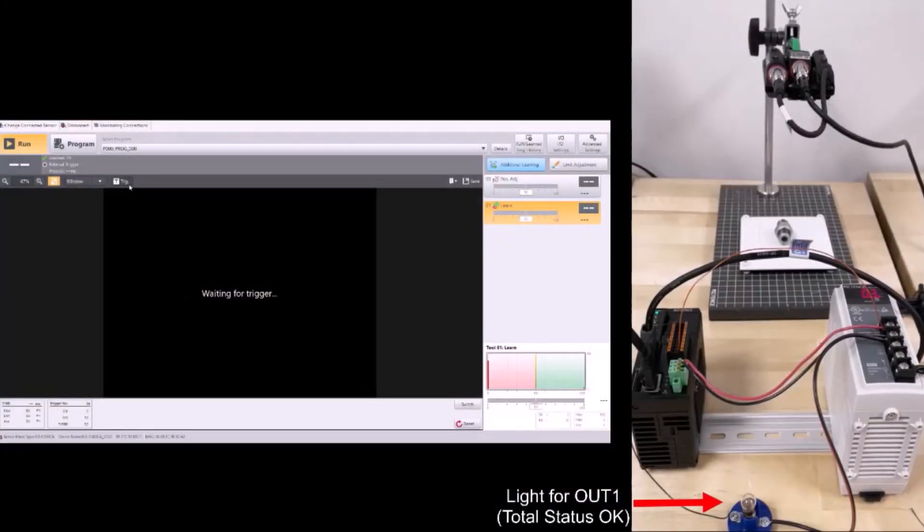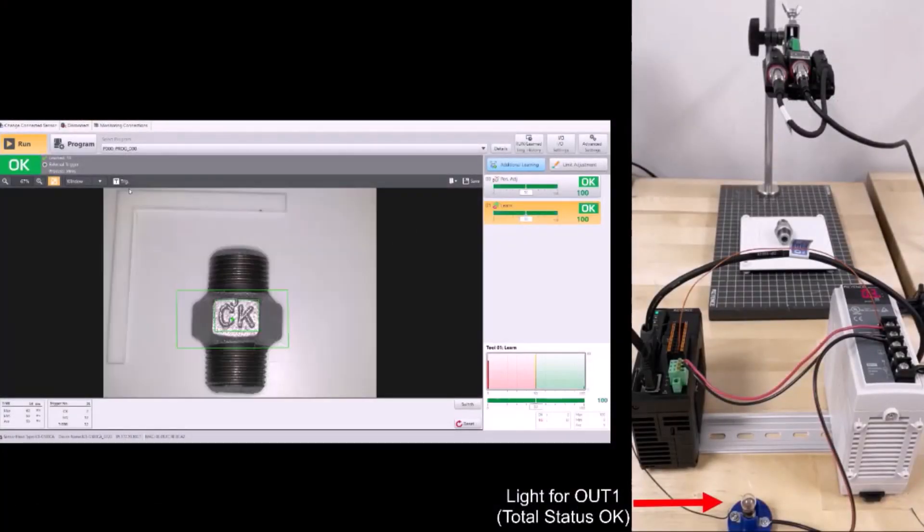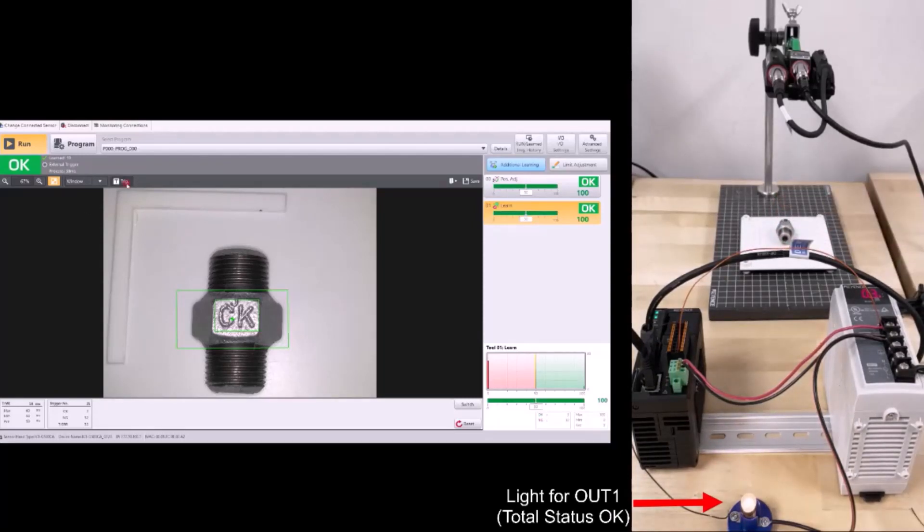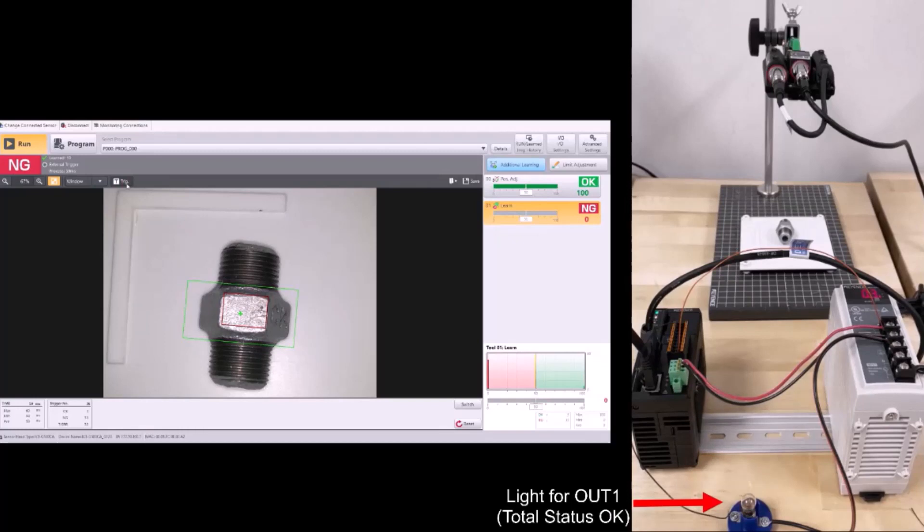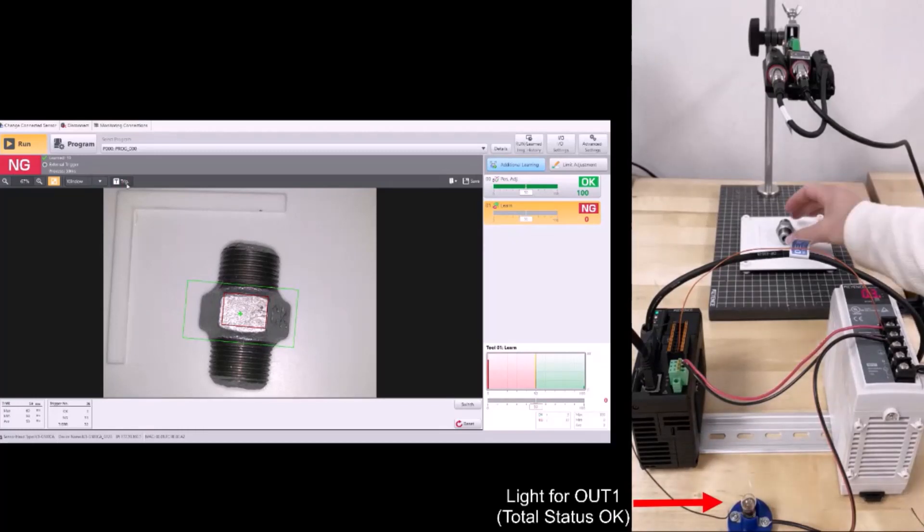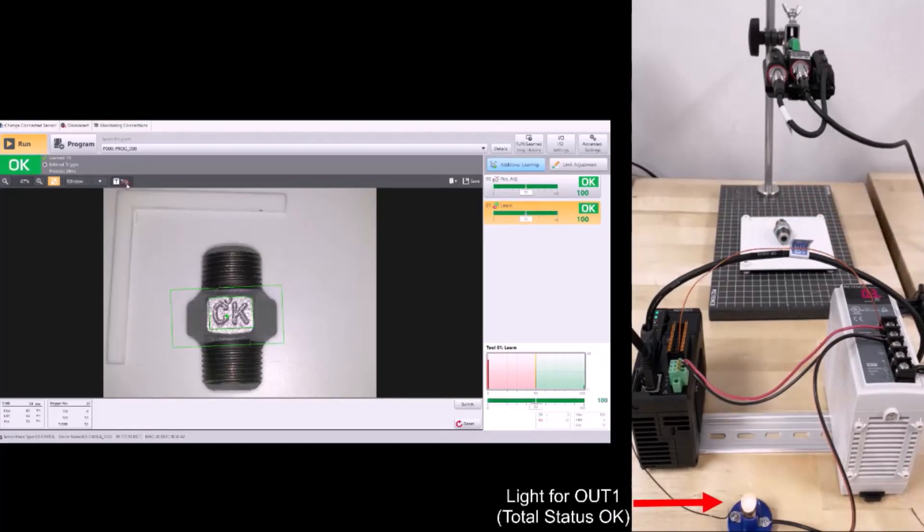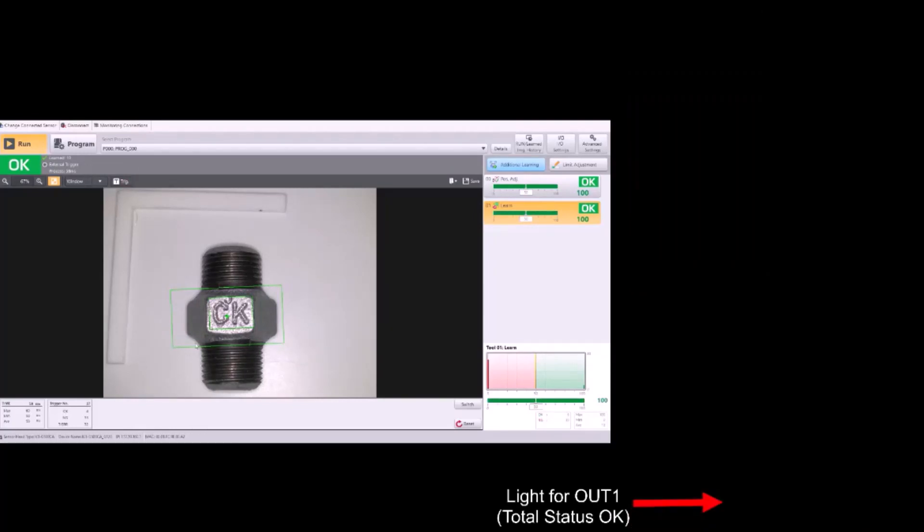So now I have a side-by-side, and you can see as I get a good result, my light turns on. When I get a bad result, that light turns off, and you can see this is showing a correctly working output for a PNP setup.